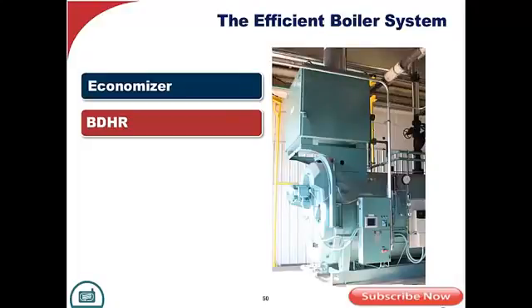Also, take a look at ways that we can improve the overall efficiency of that boiler. Remember, a boiler can only do so much. You get 84, 85% fuel to steam efficiency out of a boiler. It's done about all it can do. So if I want to get that up to above 85%, let's say, I've got to think about external things that I can employ.